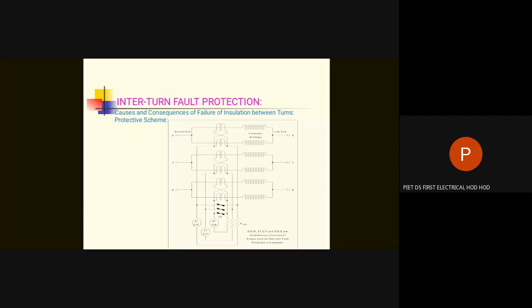So what is used is a kind of transverse differential protection. That means once again 6 more CTs are used: 6 for the differential protection we have seen, and 6 for inter-turn differential. They are wired like this, and it is a kind of differential protection only, 87GIR, 87GIY and 87GIB. If there is a fault between two turns of the same phase, you can see there are two windings of R phase shown. If there is a short circuit between them, the current flowing in the upper and lower paths of the inter-turn differential will be different, that will give rise to current flowing to the relay, and the relay will operate.